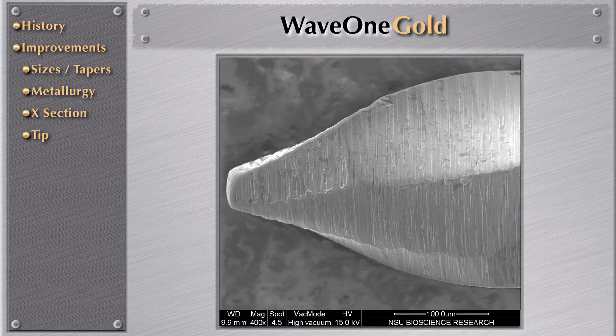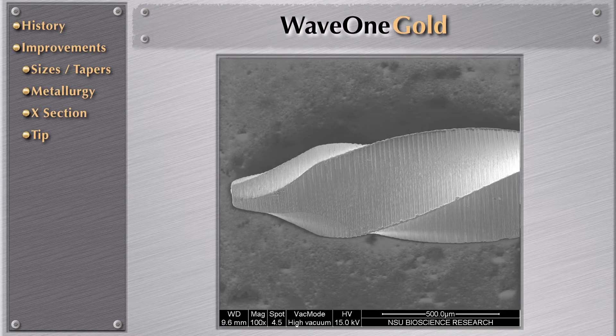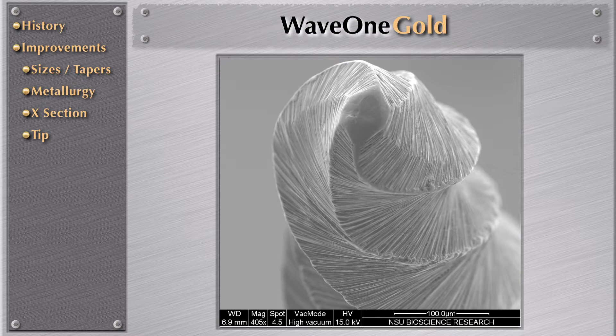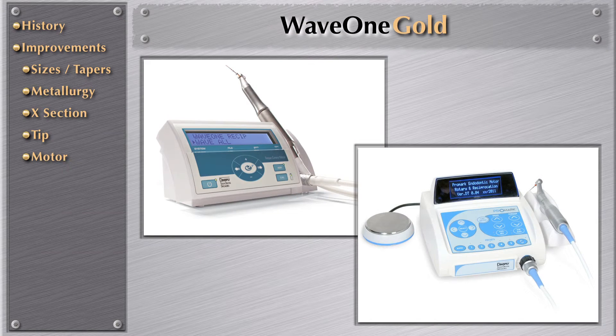Now we have the tip — also a big improvement. In the past, we had a non-cutting tip, a guiding tip, and now we have a semi-active tip, as you can see with these scanning electron microscopy photos. This means the file will advance inside the canal with much less effort, without applying the same amount of apical pressure as before. The beauty of that is we do not need to change motors — we can continue using the same motors as WaveOne, but it's very important to understand that it must be the motors designed by the manufacturer of WaveOne and WaveOne Gold.